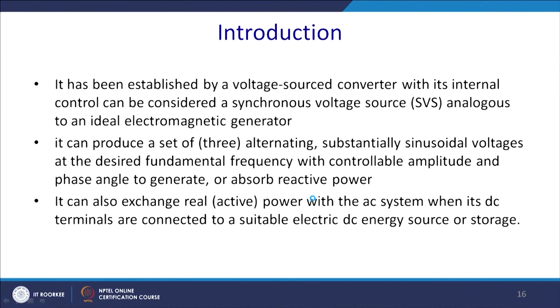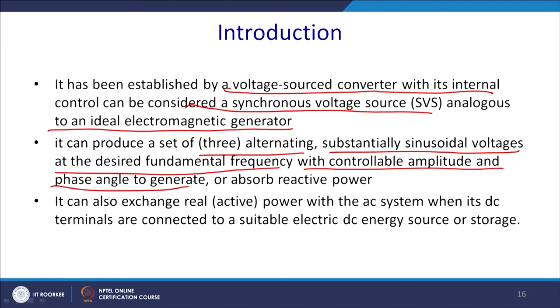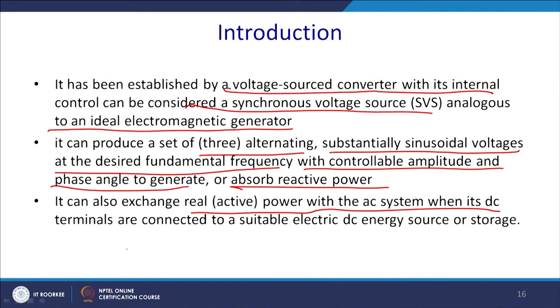It has been established that a voltage source converter with internal control can be considered as a synchronous voltage source, analogous to an ideal electromagnetic generator without any rotating part and thus without any inertia. It can produce a set of three alternating sinusoidal voltages at the desired fundamental frequency with controlled amplitude and phase angle, and can generate or absorb real or reactive power. It can also exchange real power with the AC system when its DC terminals are connected to a suitable DC energy storage device.